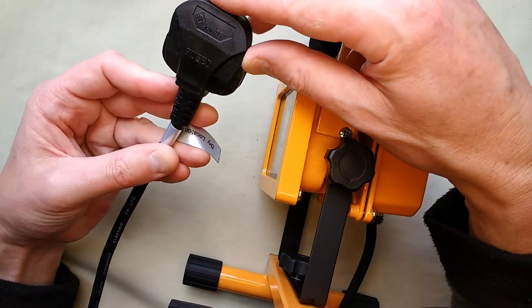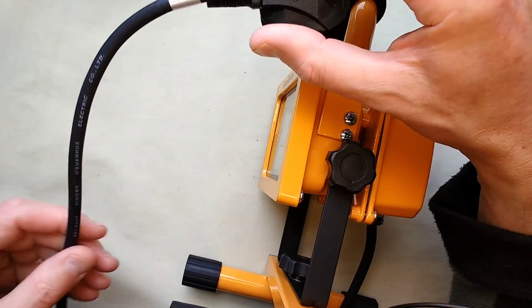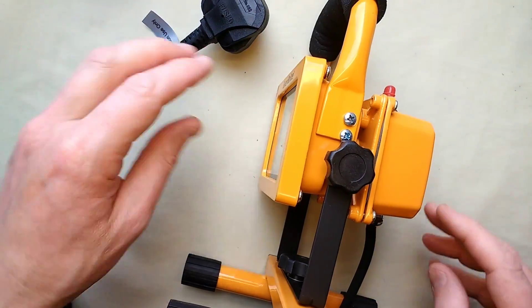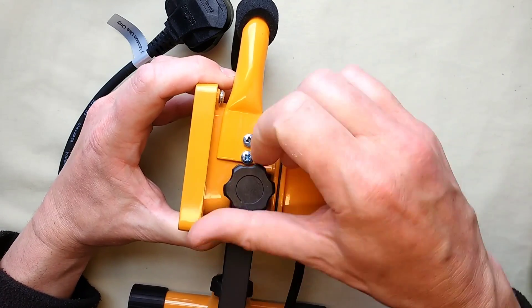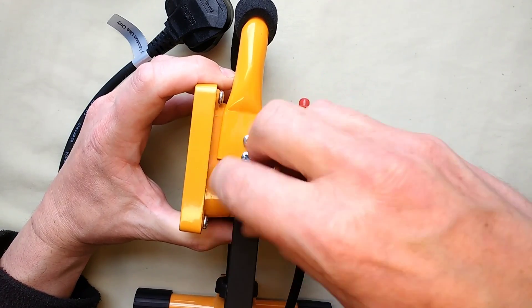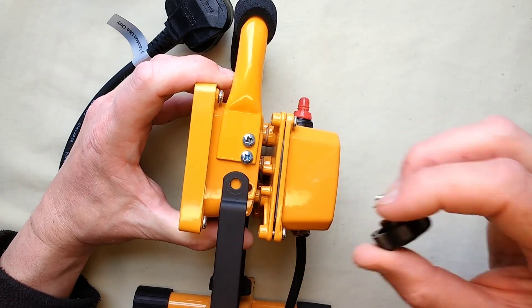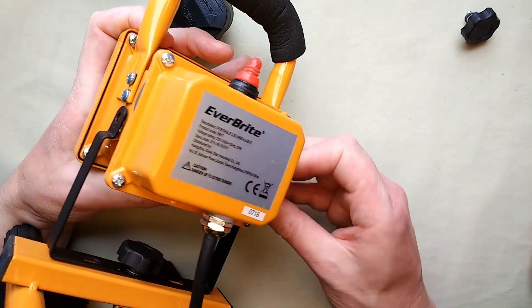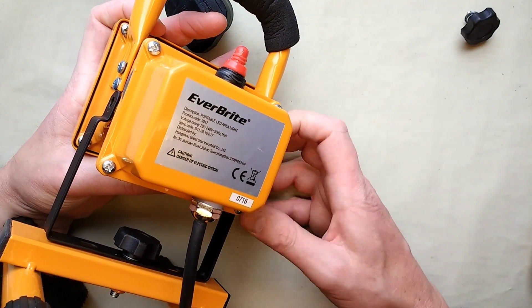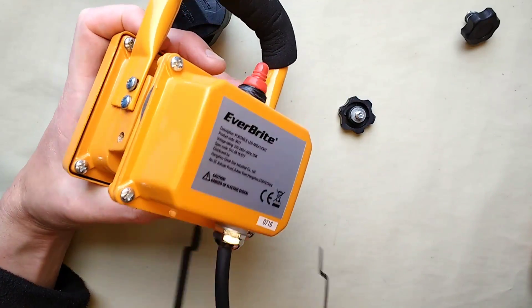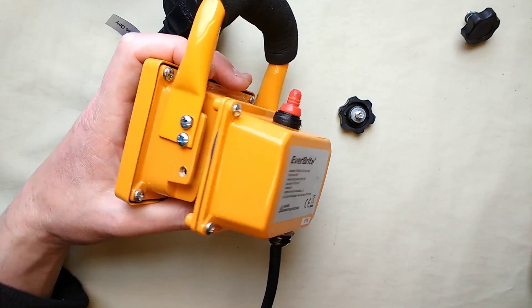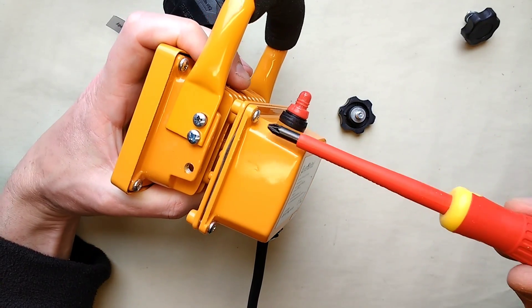Things worth noting: it comes with a proper plug, it comes with rubber flex H05 rubber flex which is a good choice for the UK. I'm just going to take this stand off because it's a bit bulky. The H05 flex is what's normally recommended for outdoor use in the UK and also recommended for site use because it's a very robust cable as opposed to PVC.